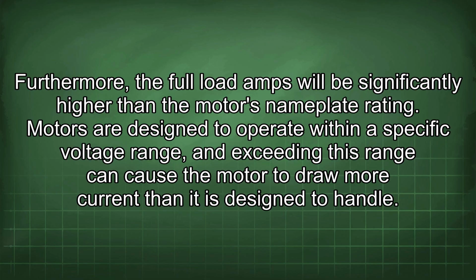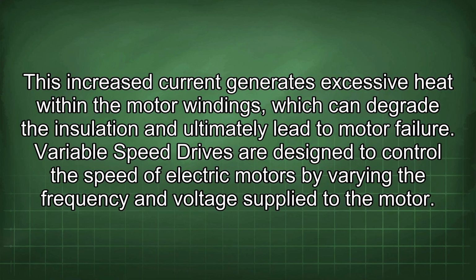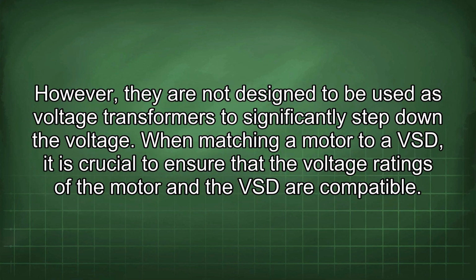Motors are designed to operate within a specific voltage range, and exceeding this range can cause the motor to draw more current than it is designed to handle. This increased current generates excessive heat within the motor windings, which can degrade the insulation and ultimately lead to motor failure. Variable speed drives are designed to control the speed of electric motors by varying the frequency and voltage supplied to the motor. However, they are not designed to be used as voltage transformers to significantly step down the voltage.